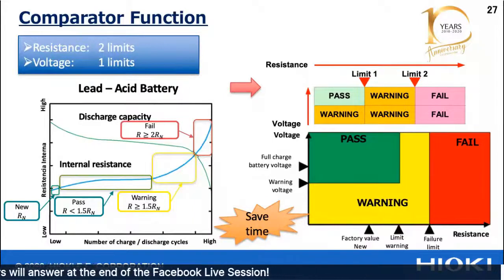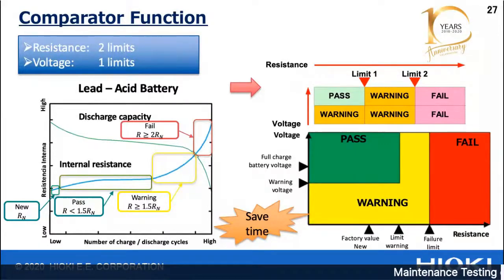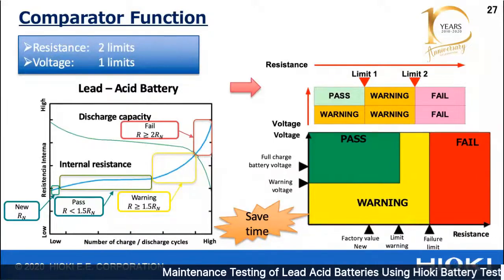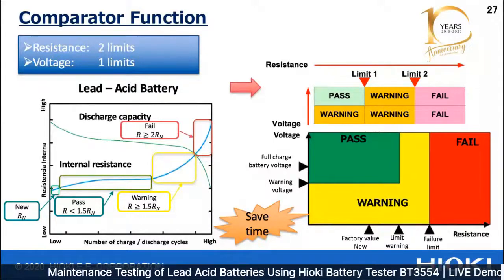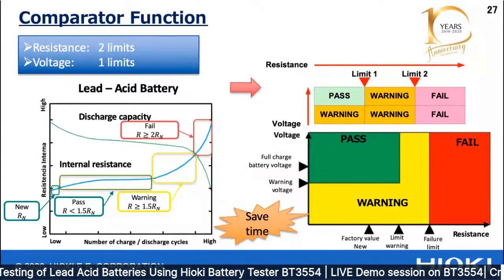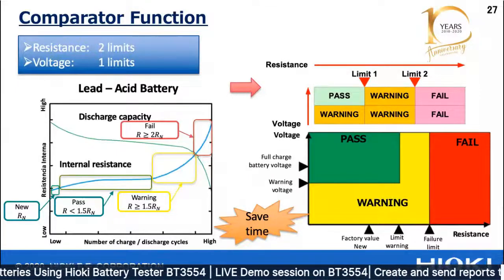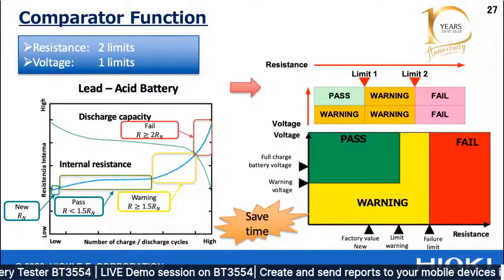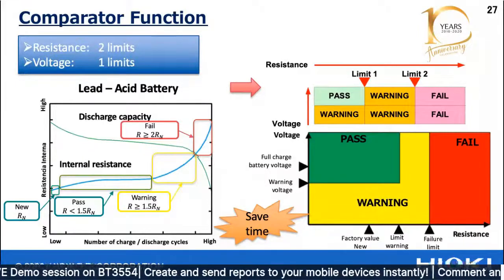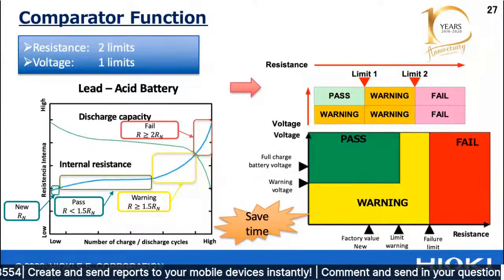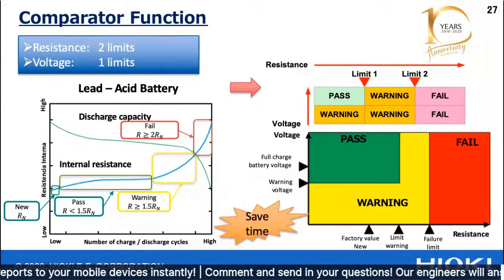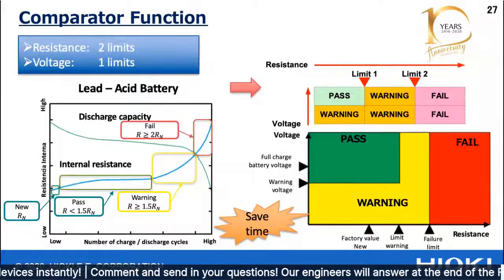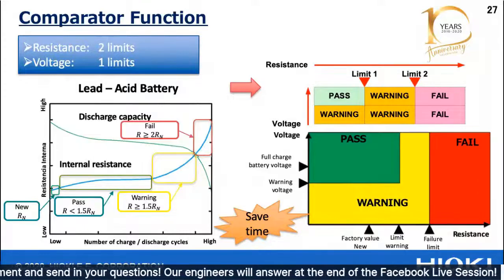It will show a warning when the measured resistance is greater than or equal to 1.5 times the reference value, and a fail when the measured resistance is greater than or equal to 2 times the reference value. That's why the reference value is very important, because you need to set it into the battery tester so it can calculate whether it's a pass, warning, or fail.